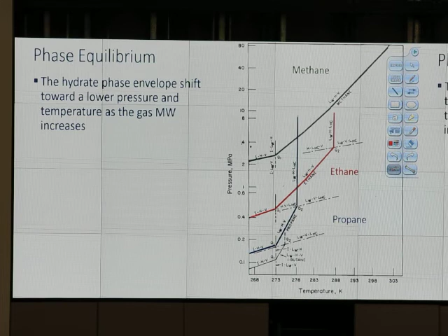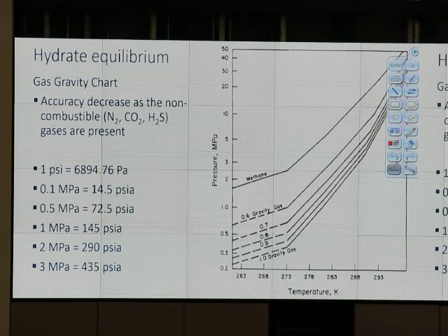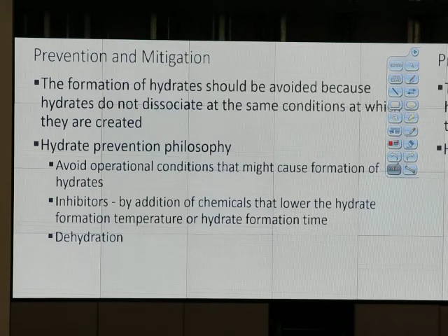So hydrate formation should be avoided. Hydrate do not dissociate at the same condition with when they are created. This means if we enter the hydrate phase envelope over here, this point, and the temperature go down, pressure maybe stay the same, and we form hydrate in this part. When we increase the temperature, it doesn't mean that hydrate start to melt at that point or melt completely at that point. Okay, so the temperature that hydrate may melt completely is a little bit outside the phase envelope. Okay, so we should avoid hydrate. We have the equipment to heat gas up so that hydrate won't form when it's cold.